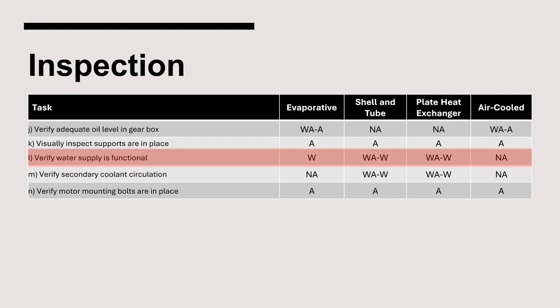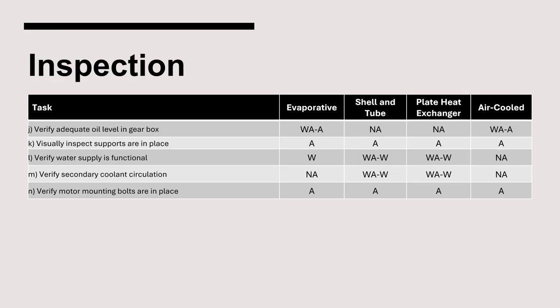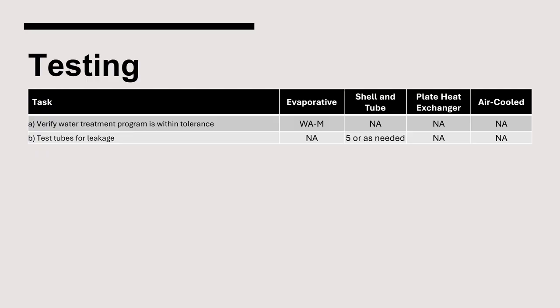Verify the water supply for the condenser is functional. This can be accomplished by observing the water level inside the condenser. Next, verify the motor mounting bolts are in place. The pump motor is secured horizontally to the condenser. Ensure to inspect fan motor mounting bolts as well. Testing requirements for evaporative condensers include verifying the water treatment program is within tolerance. Lastly, testing tubes for leakage every five years or as needed is required for shell and tube condensers.